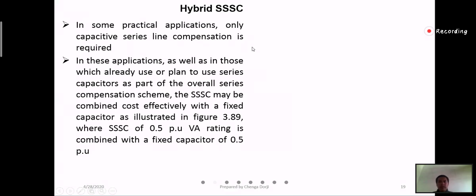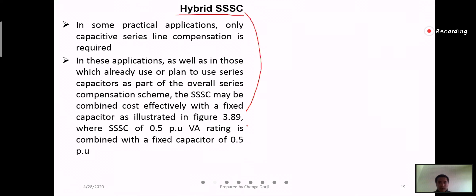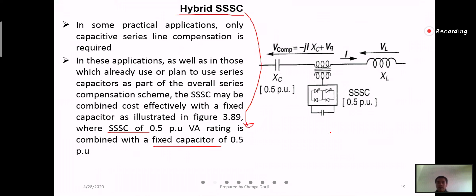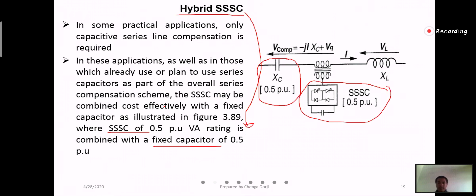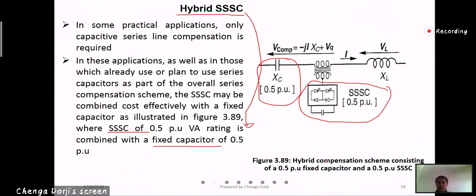In some practical applications, only capacitive series line compensation is required. In such cases, you can use a combination of a series capacitor and a fixed capacitor. If you have this SSSC with a fixed capacitor, then such a scheme is called the Hybrid SSSC — a combination of SSSC with fixed capacitor connected in series with the line.